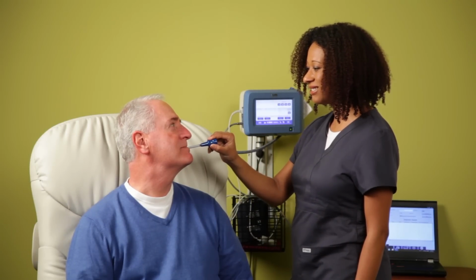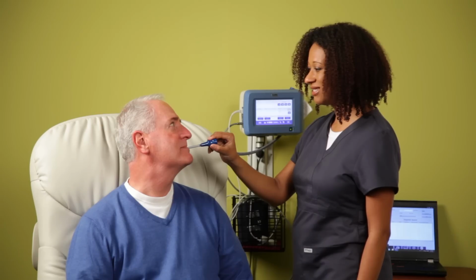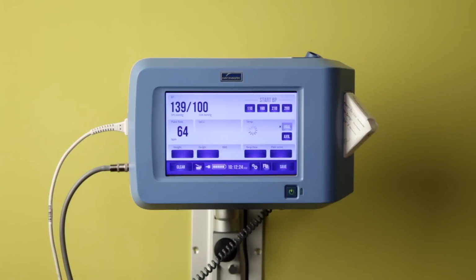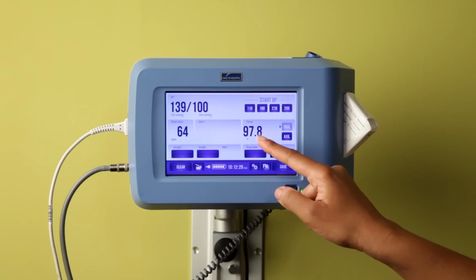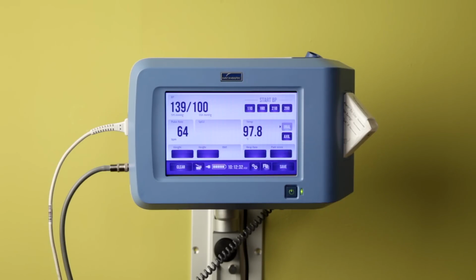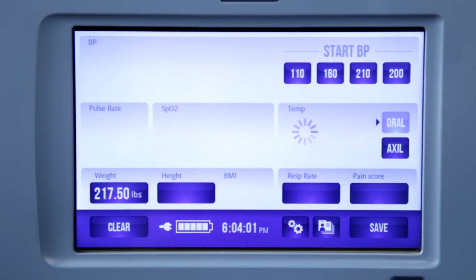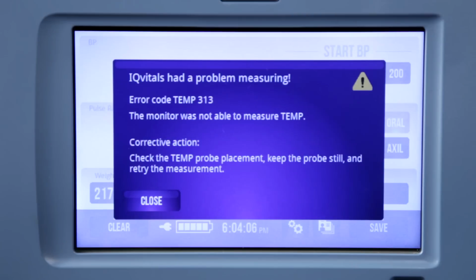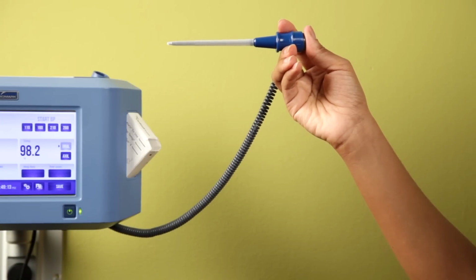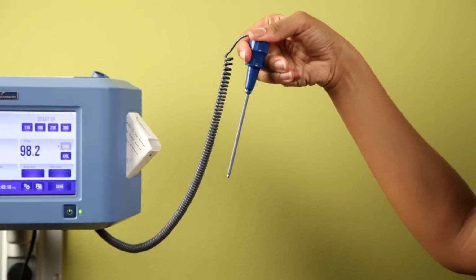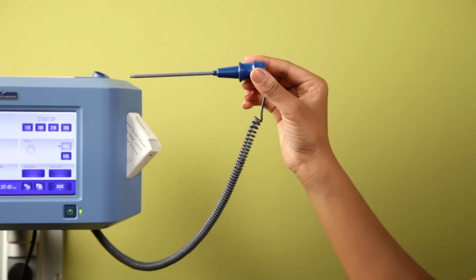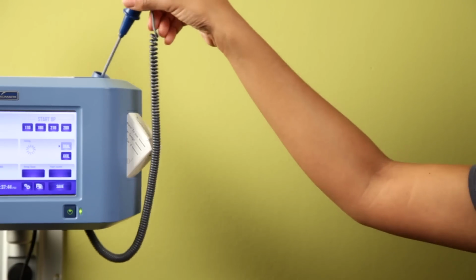Hold the probe during the entire measurement procedure, keeping the probe in contact with tissue at all times. During temperature measurement, the in progress wheel will appear. An audible tone will sound when the measurement is complete, and the patient's temperature will appear below the temp button on the screen. If there is a delay of 1 minute or longer from the time the probe is taken out of the well until a temperature is taken, the device will not take a temperature. You must put the probe back in the storage well and remove it again to reset the thermometer. To remove the probe cover, hold the probe as you would a syringe and press the eject button at the top of the probe. Place the probe back in the storage well to reset the thermometer for the next patient.